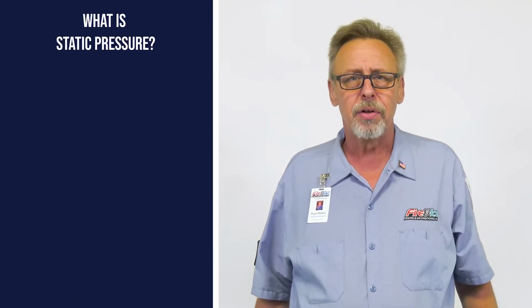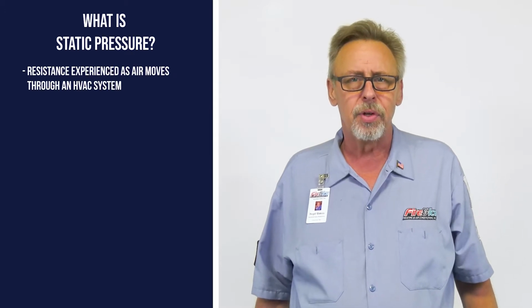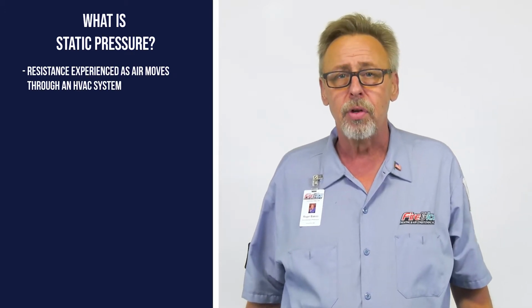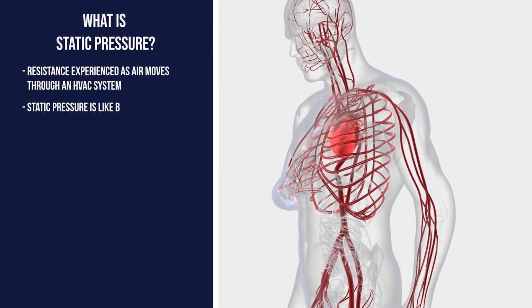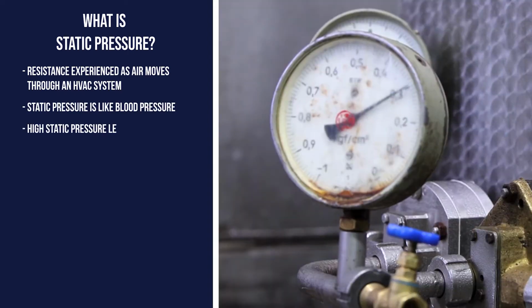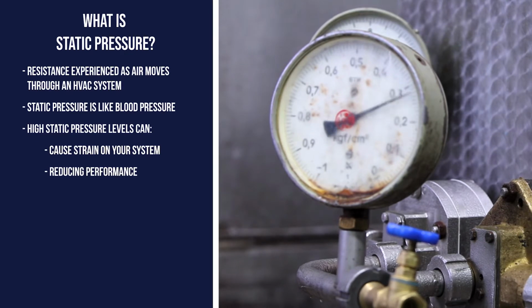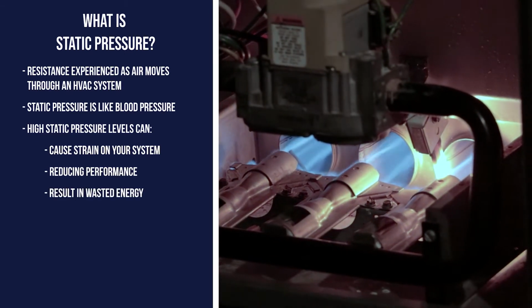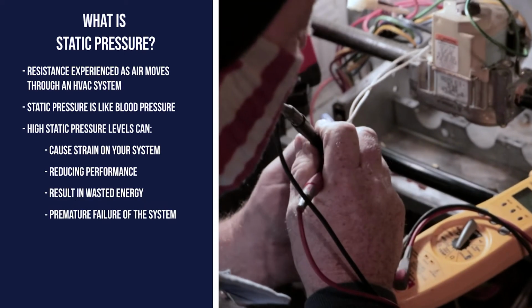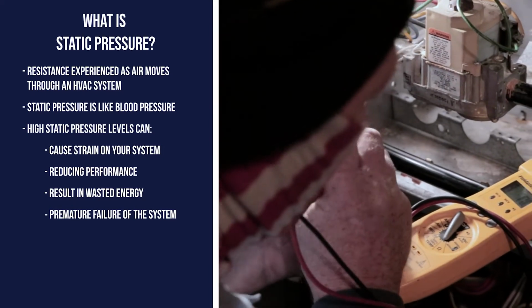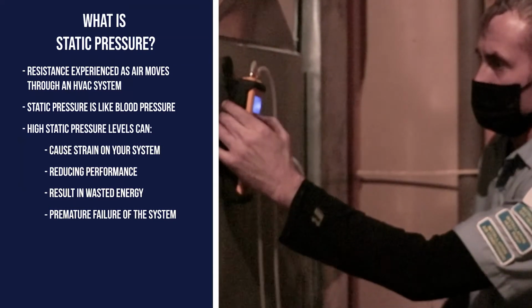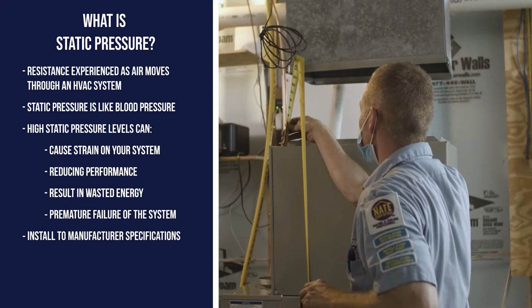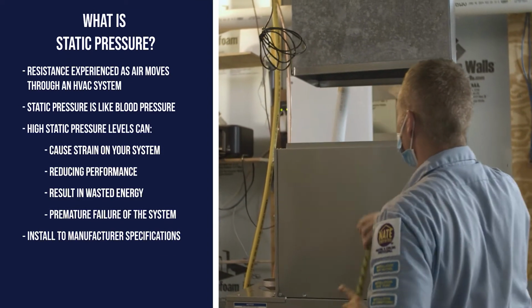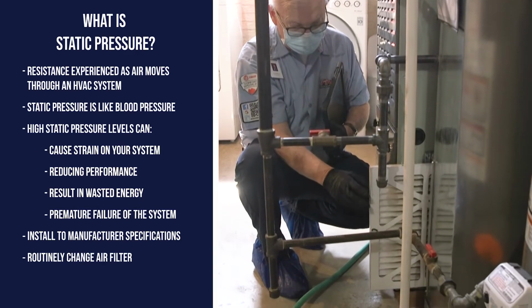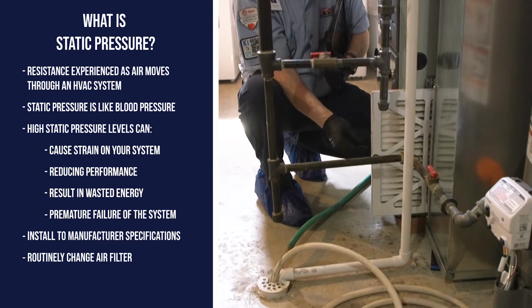What is static pressure? Let's begin and determine what static pressure is. Simply put, it is the resistance experienced by air as it passes through your HVAC system. It's a lot like blood pressure in your body. Too much static pressure can cause strain on your system, reducing its performance and can result in wasted energy. If left untreated, it can result in premature failure of the system. The best way to maintain optimal static pressure is to have properly sized equipment and ductwork installed correctly in your home. Additionally, regularly changing your air filter will help maintain static pressure levels.